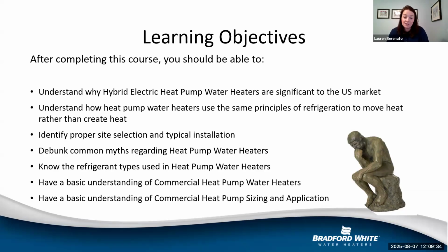Another thing that could be a challenge: if you specify a heat pump today, but the job doesn't go on for 18 months to 36 months from now, designs could change. So just keep an eye on that, especially contact the manufacturer, contact your local rep who's representing the water heater manufacturer, as well as look at the specification sheets. The specification sheets will be up to date. They will tell you what to do with sizing, but that's been one of the biggest things that we have noticed is that the unit itself has been changing for some manufacturers between specification as well as installation. So what's being installed could be slightly different than what you specified.